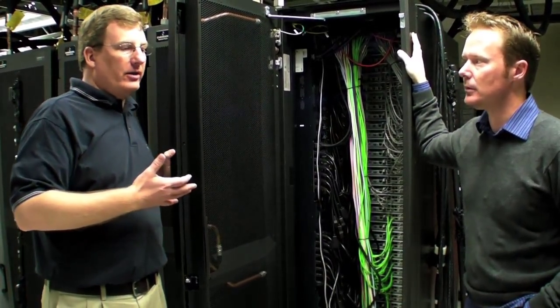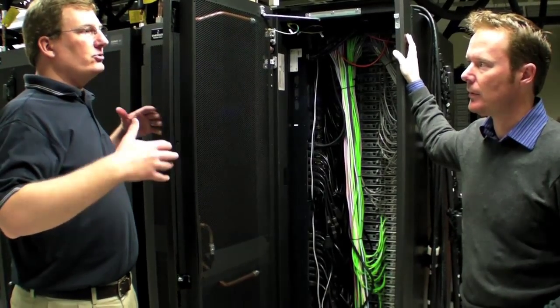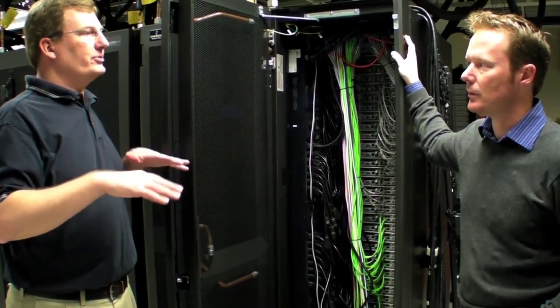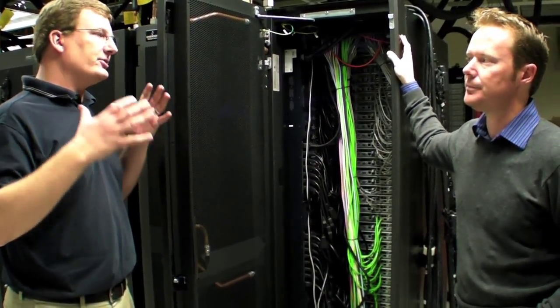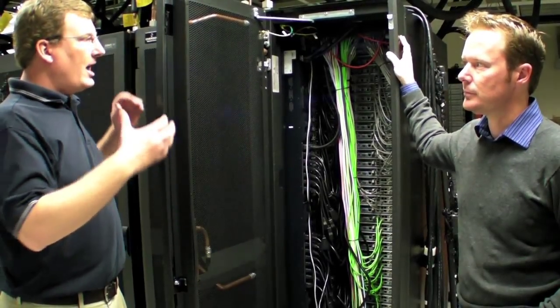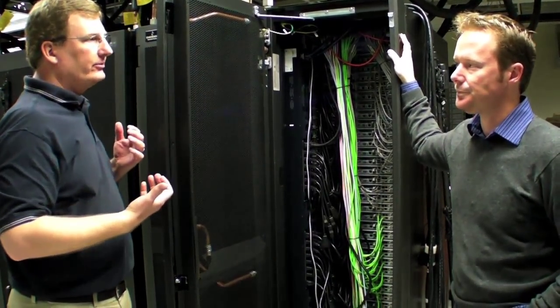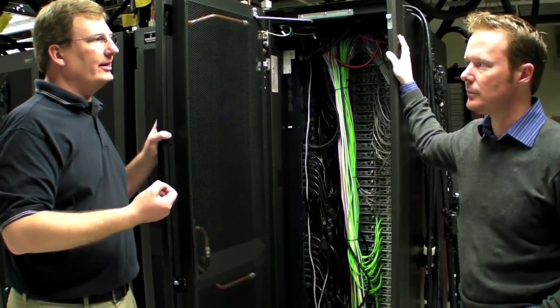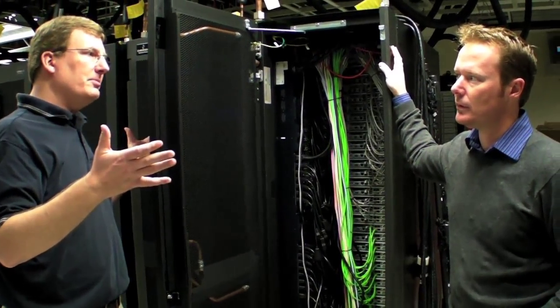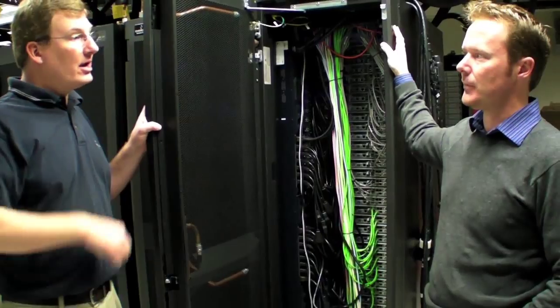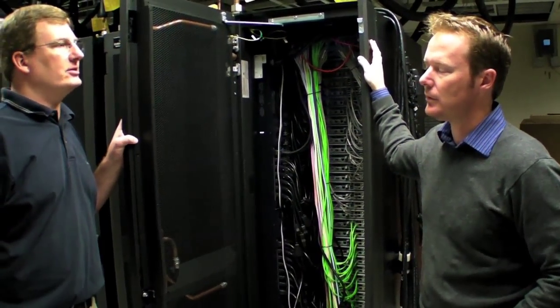By having the room neutral environment, if you were to build a data center using this kind of configuration, the advantage is you're just trying to control the humidity in the room. So you don't need all the CRACs and everything else that you would have for moving air. As long as there's an air supply going through the door, and because we're in room neutral conditions, you just make sure you maintain the humidity and everything else takes care of itself. So you don't need the number of CRACs that you normally do.